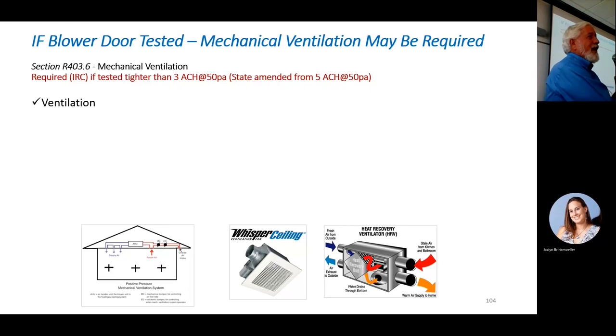Now, is that a bad thing to have a fan running all the time? Now, I'm not a big fan of what we call positive pressure ventilation with a furnace. And here it is with a furnace where we're sucking in a certain amount of outside air. We balance it to the 50 CFM, and we just let that blower run all the time. If you have a good high efficiency blower with an ECM motor and everything, it's not a bad thing to have it running on a low CFM, always filtering, right? And bringing in a little bit of air. But that's a positive pressure system, so what it does is it pushes contaminants into our wall cavities. So it's not my favorite method.